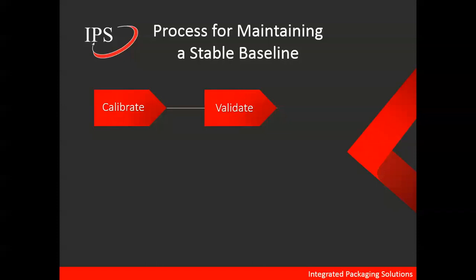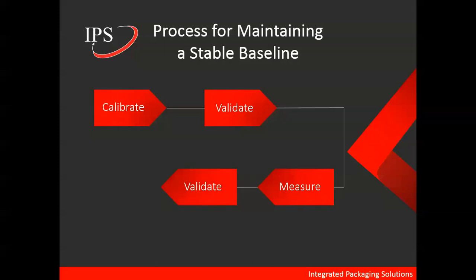So after the validation process, we recommend that the tool is measured. Now, after measurement and before any other measurement, we always recommend that you validate again. The ToolScan 2.0 has the temperature probes integrated into it. The way that we automatically validate before every measurement is to check the temperature at which we are going to measure and compare that to the temperature at which the gauge was calibrated. If those temperatures are close enough within our tolerance level, then we go ahead and measure again. However, if the temperature has changed, our validation process says it's time to calibrate again. And so that's what we do. So the validation piece is an important component of the measurement process.